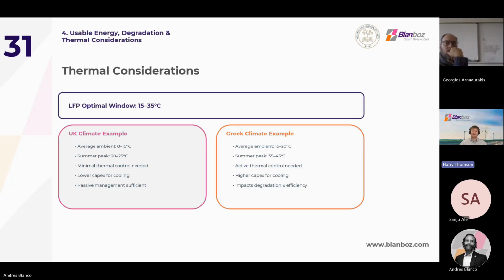This means higher capex up front for stronger cooling systems. It impacts the efficiency, as there's higher auxiliary consumption due to more cooling power needed, and increases degradation due to the higher temperatures. So that's a lot to think about when designing the site.